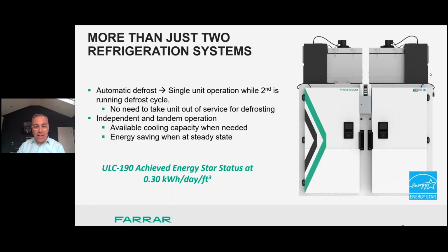Unlike freezers that require manual defrosting, the defrost rate and time on our ULC can be set while the unit is in service. That means there's no reason to take the freezer out of service for 2 or 3 days while you wait for it to thaw and put it back into service. So no loss to recovery times, no degradation of uniformity due to icing. All you really have to do is vacuum with a shop vac the snow that accumulates at the bottom of our freezer. And that snow happens anytime that you don't remove humidity from your environment.